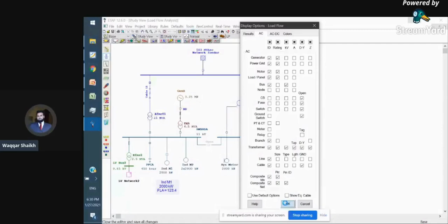If you want to see network building options like the generator or power grid, and what type of information you want the screen to display, you have to go into the AC tab. For example, if I have modeled a transformer in the network and I want additional information shown on the display in load flow mode, I can enable features here like KV, tap, grounding configuration, and impedance. If I click OK, this information will appear just beneath the transformer. So the display option enables me to show more or less information on the screen depending on my requirements. Normally in study modes like load flow, we do not require so much information about the equipment, since we are more interested in seeing the results, so at that time we don't show much of that information.